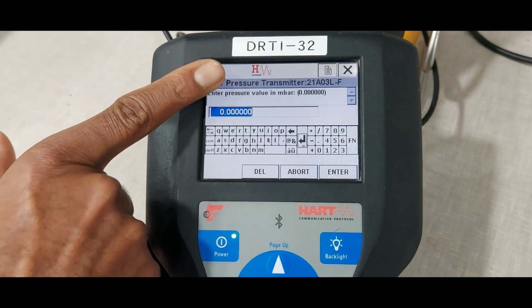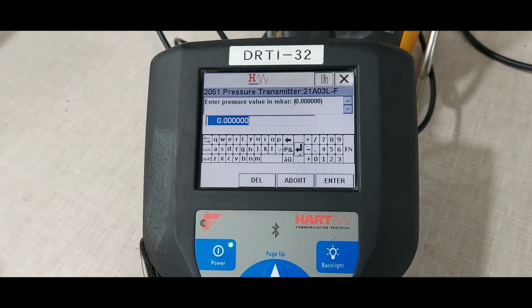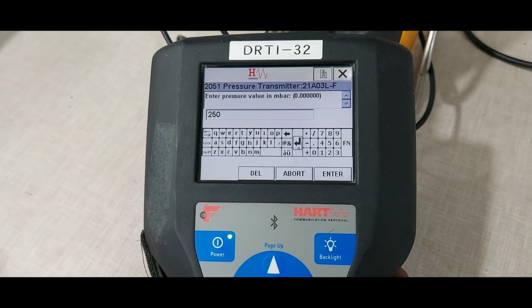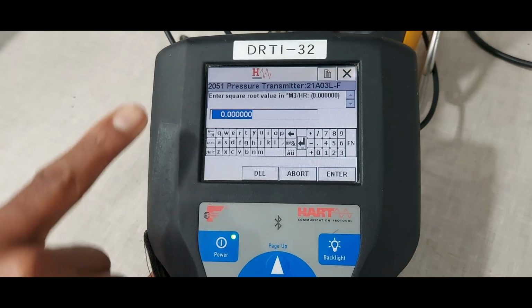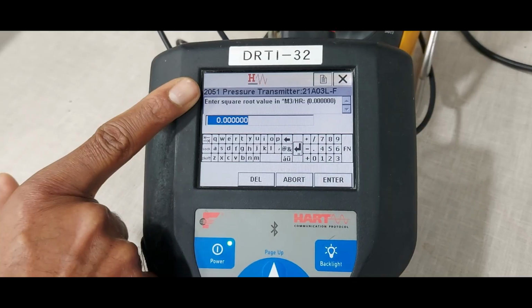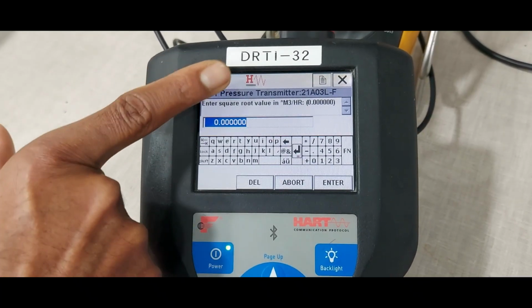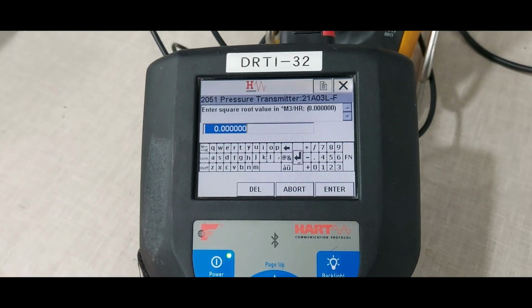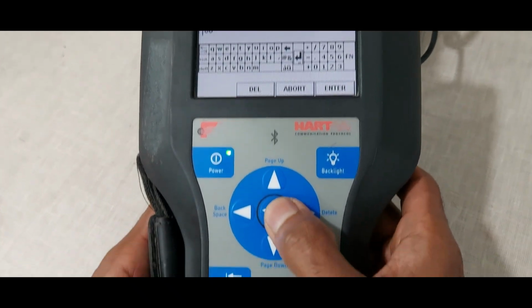Next, enter the pressure upper value. What is the pressure value? 250 millibar. Enter. Next, enter the square root value in meter cube per hour. What is it? 80. That is the square root value.